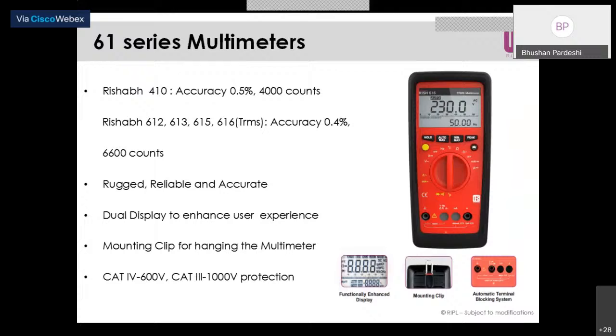Those values are taken into account during calculations, and that is nothing but the true RMS—the root mean square of the waveform including harmonic values. The count in the RISH 61 series is 6,600, whereas the count in the 410 is only 4,000.